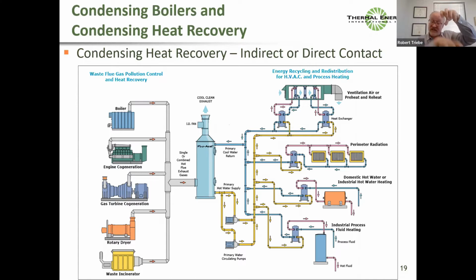So the thinking and the integration of these technologies should go well beyond "I'm going to recover from the boiler to deliver to the boiler," even go beyond "I'm going to keep my heat recovery project in the boiler plant," or "I'm going to keep my heat recovery from a dryer and just heat that dryer." You should look more broadly in the facility and see what you could do with a free hot water circuit. A few hundred feet of piping is not often a project killer, especially in today's world of sustainability and carbon reduction.